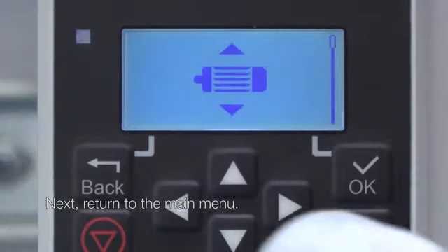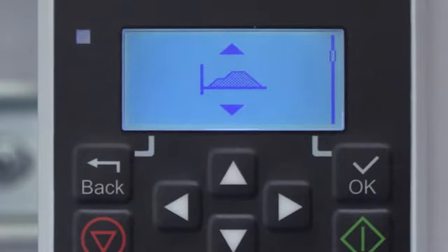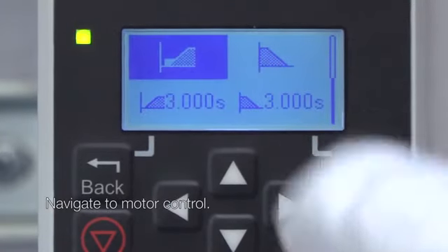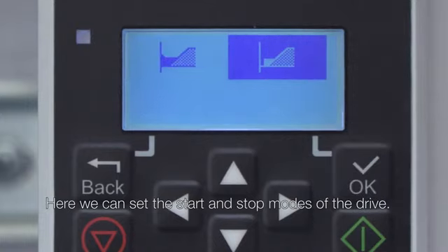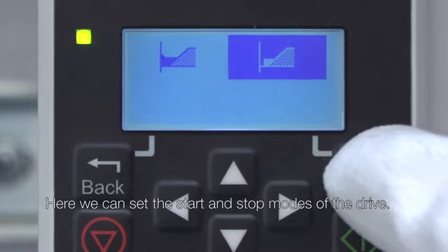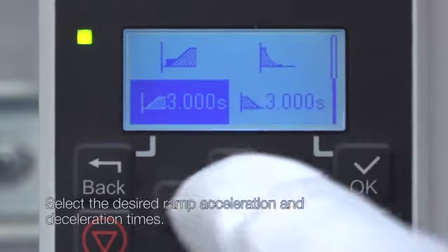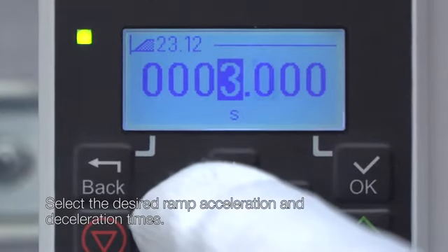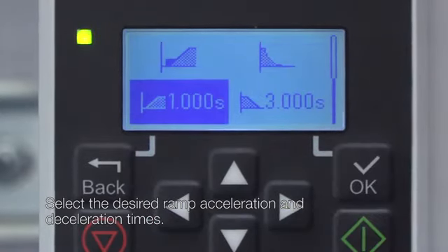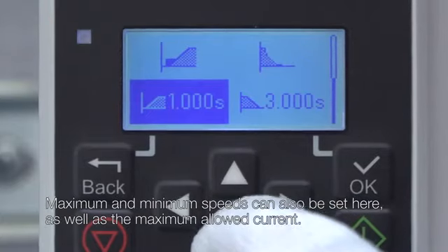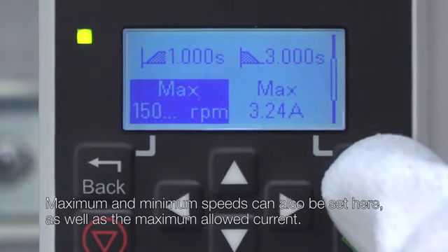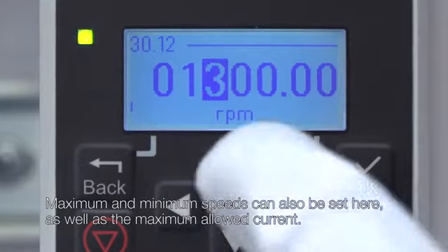Next, return to the main menu. Navigate to Motor Control. Here we can set the start and stop modes of the drive. Select the desired ramp acceleration and deceleration times. Maximum and minimum speeds can also be set here, as well as the maximum allowed current.